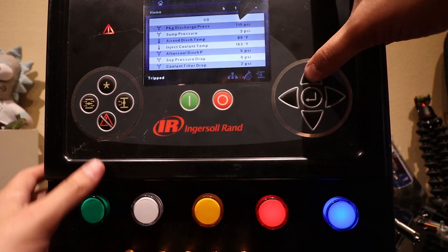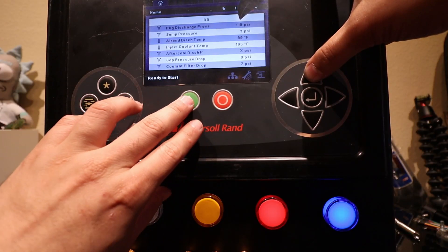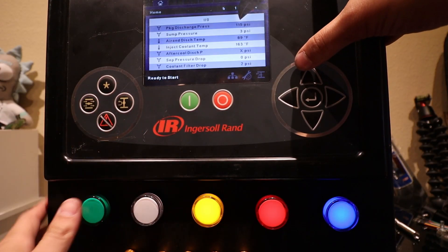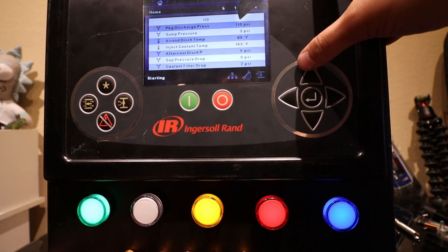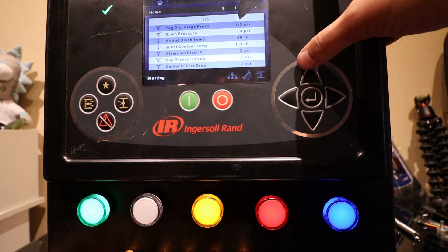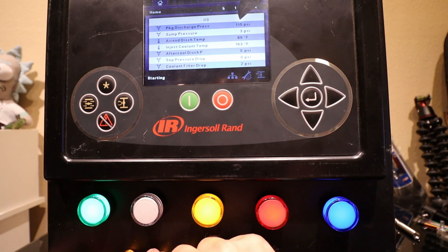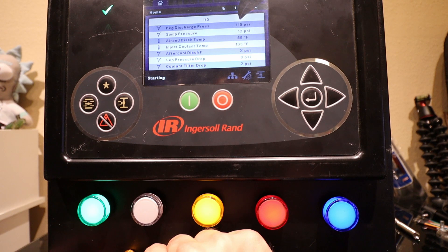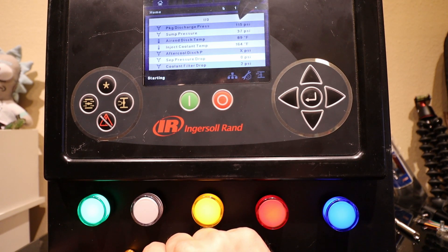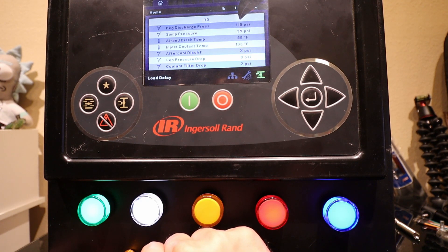These two lights are partially on, and I'm going to tell you why in just a second. Hit the start button, the unit's starting. The green and yellow light go on, that's the KM3 contactor. It actually makes KM1 go on, and then after 10 seconds it goes off and the white light goes on which is KM2.